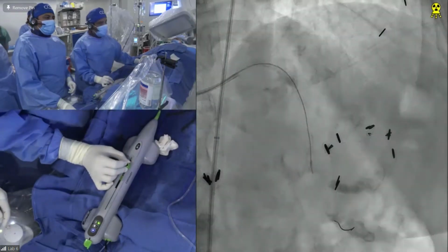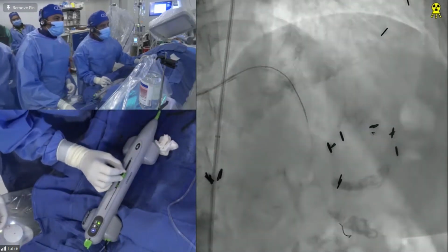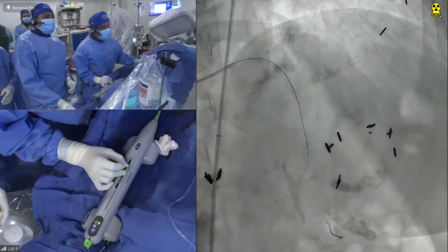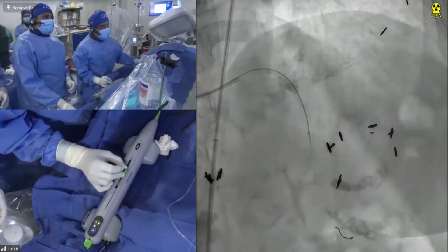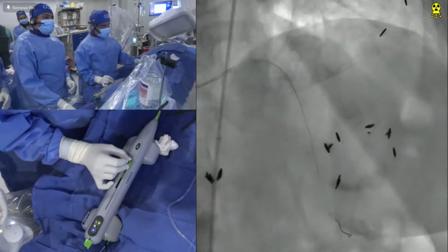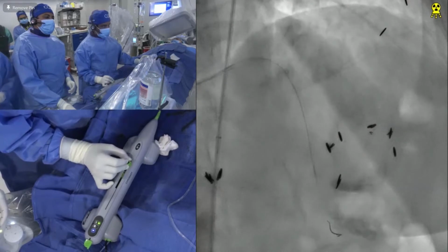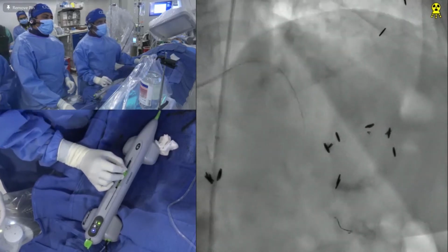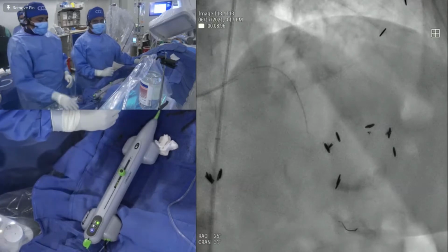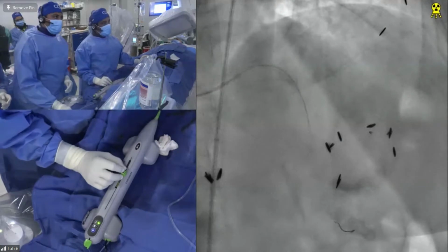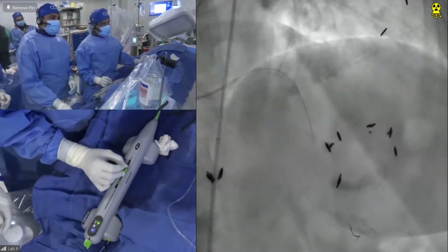You see that going very nicely, taking the course of the vessel. The key issue is to go slow. Why are you doing it so slow? Very slow. That's the slowest that you can. Very, very slow. Especially right over the lesion, right? Exactly. It is an orbital atherectomy, so it takes time. If you want to avoid complications, just go slow. Almost stand still. Slow and 80,000 RPM. Exactly.